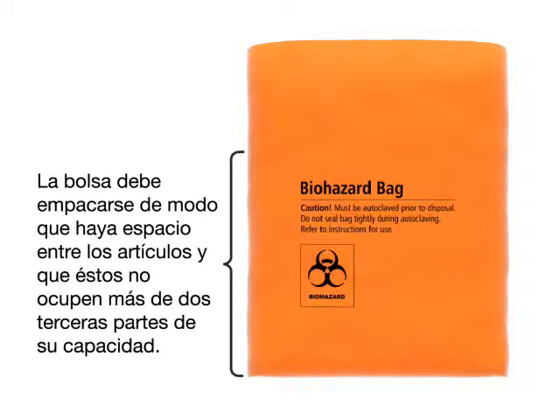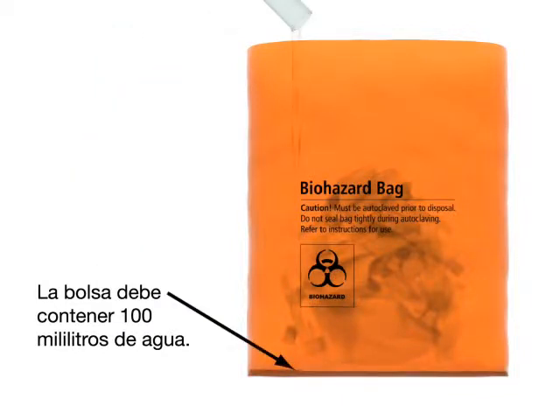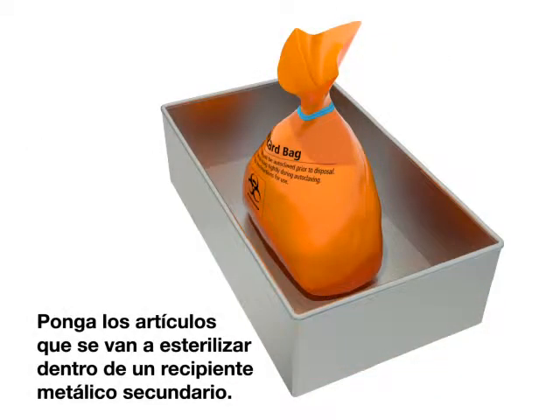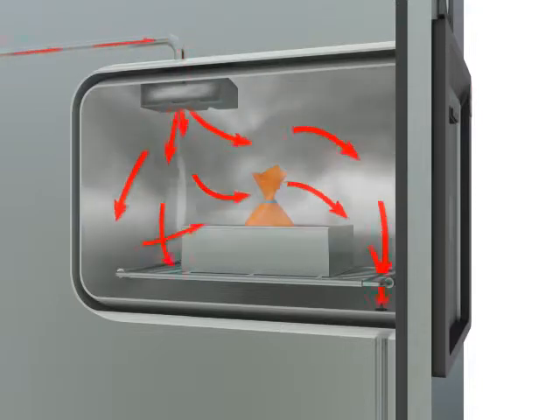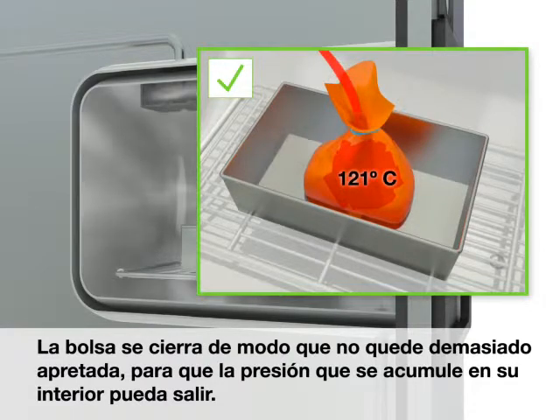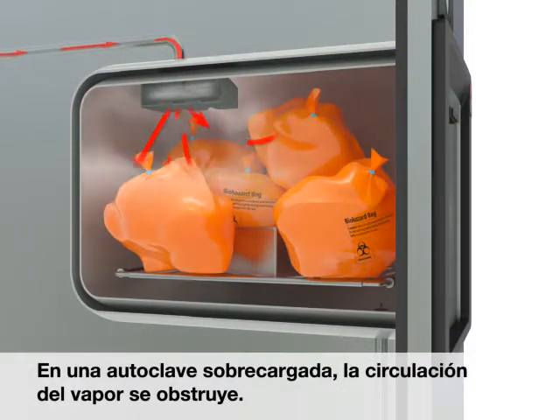The bag should be loosely packed and not more than two-thirds full, and should contain 100 milliliters of water. Close the bag loosely. Place the items to be autoclaved inside a metal secondary container. Place the pan in the center of the autoclave and do not overload the chamber. Close and seal the door. The bag is loosely closed to relieve pressure buildup inside the bag.